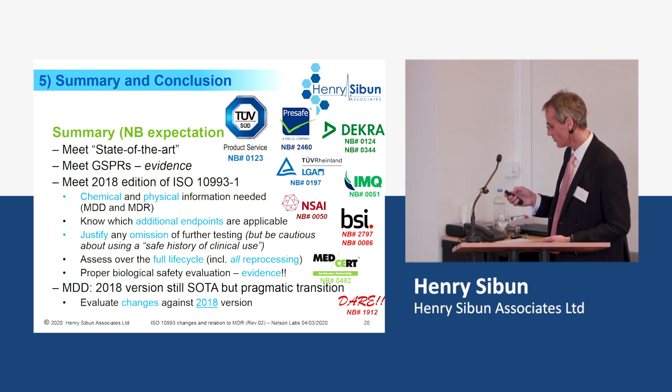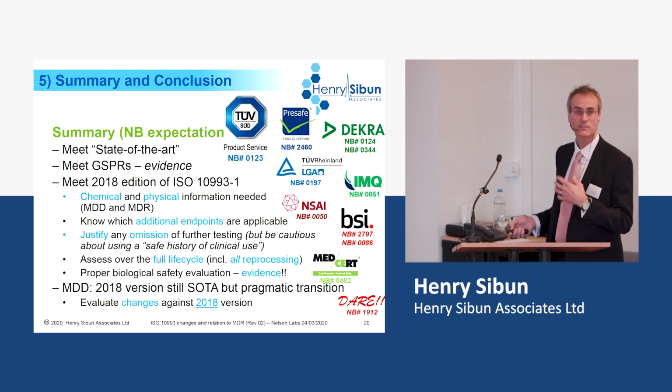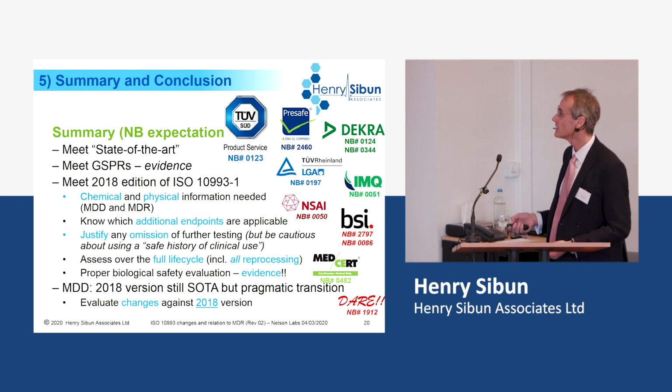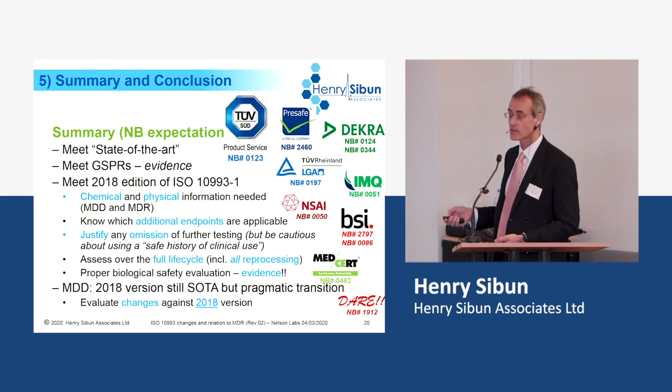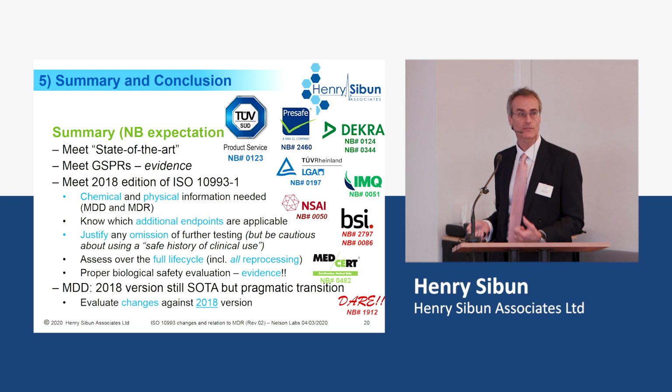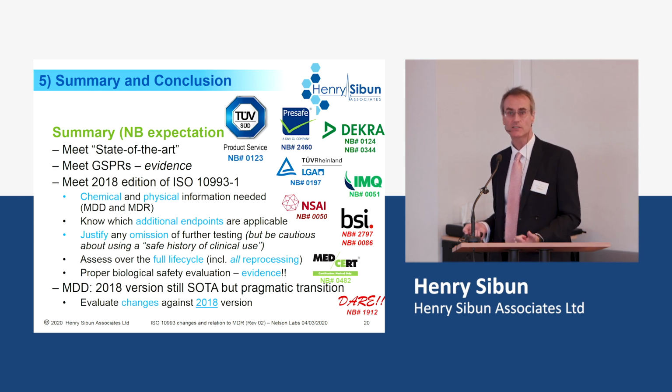And lastly, if you're working with the MDD, if you've extended your EC certificates for the next few years, state of the art is the 2018 version, but it's accepted to work with the previous version except for changes. If you make changes to your device, make sure you're following the 2018 version.